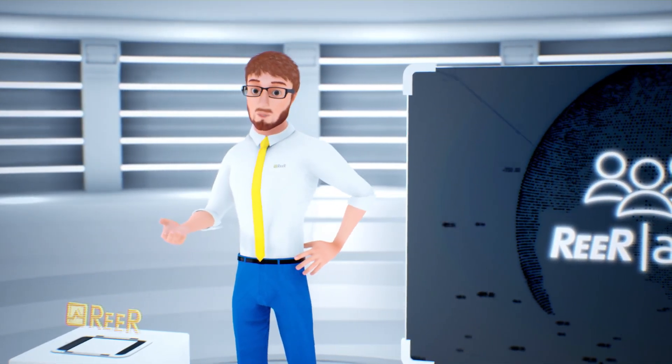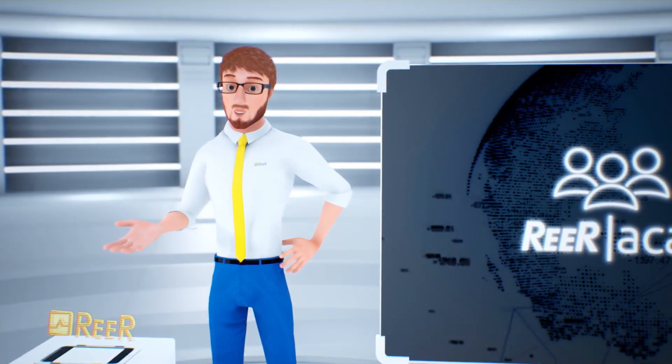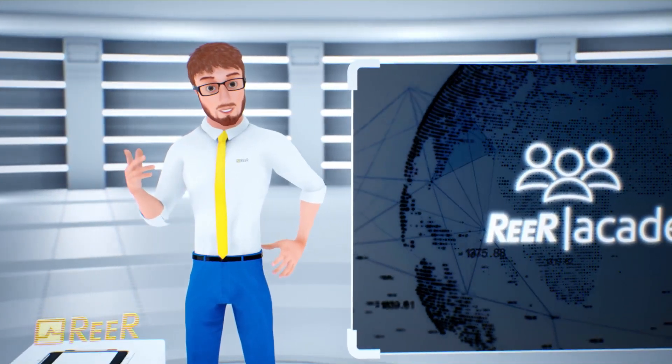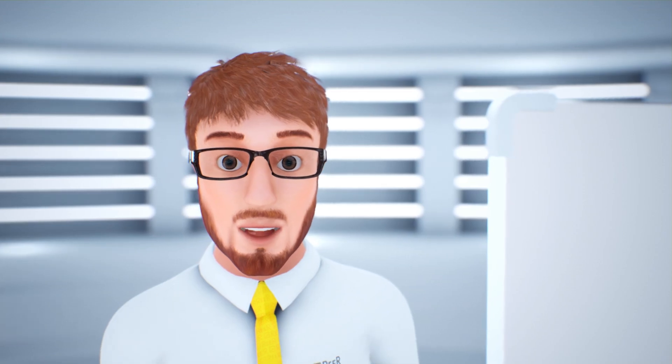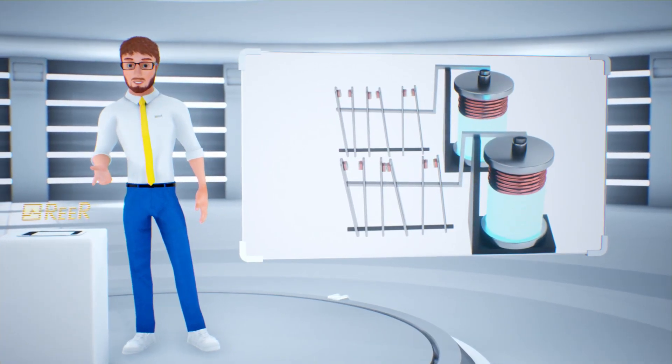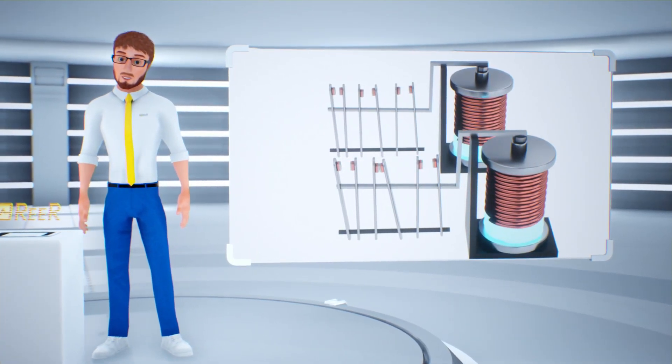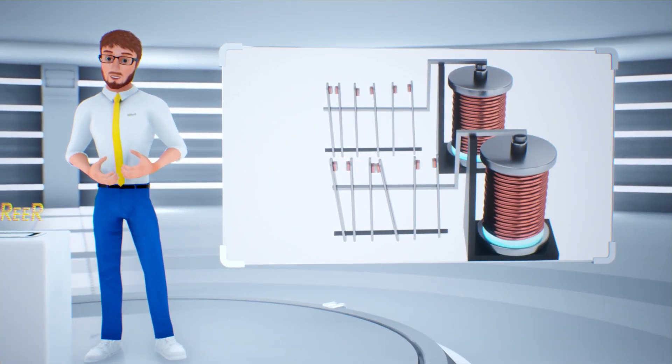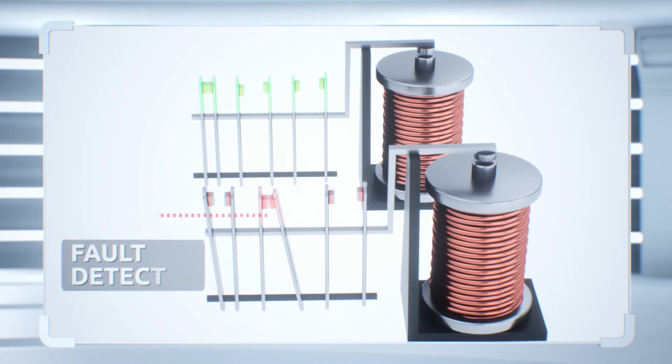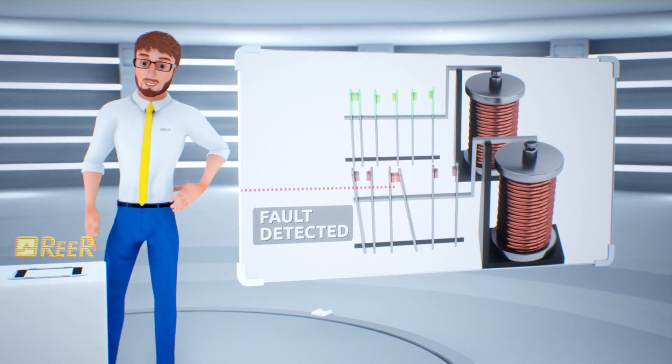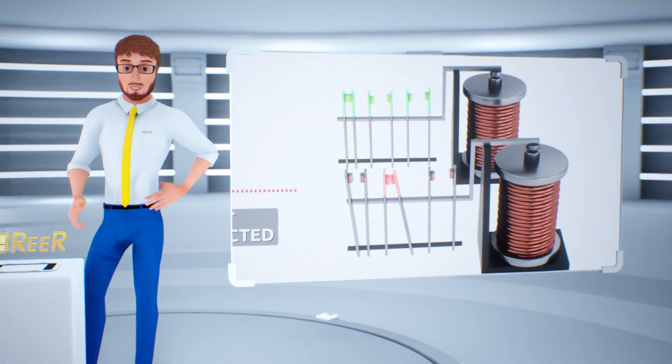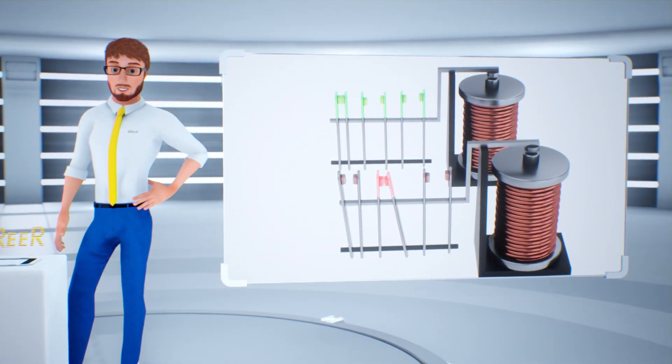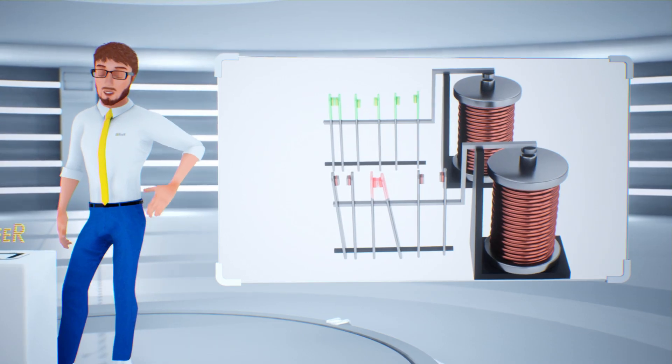When the primary contact moves to open position, the machine stops. If it remains stuck, and therefore closed, the secondary contact still opens, and in combination with a special monitoring function, detects the malfunctioning of the relay. This function is called EDM, external device monitoring, and is also known as feedback function.